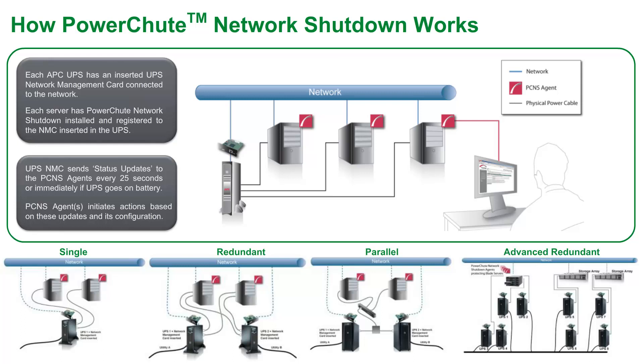PowerChute Network Shutdown supports the following UPS configurations: a single UPS protecting one or more servers; up to four UPSs configured in a redundant UPS configuration supporting one or more servers. Each UPS has the capacity to supply power to the load on its own. The first UPS provides all the power for the load, and the additional UPSs act as a reserve.